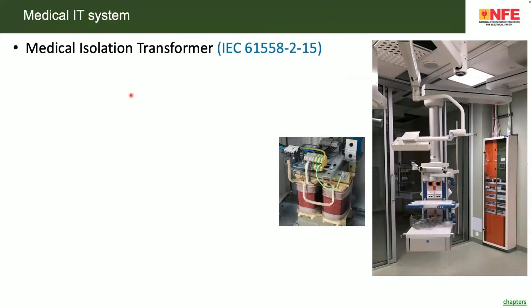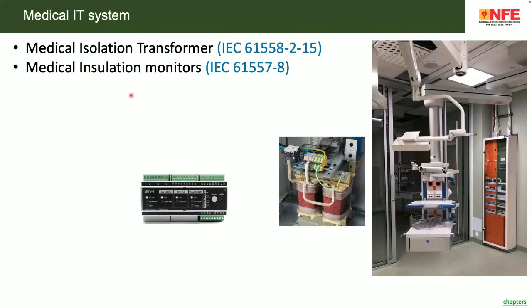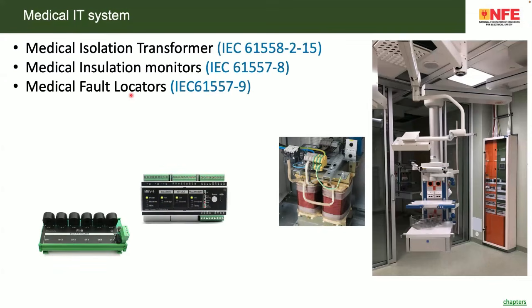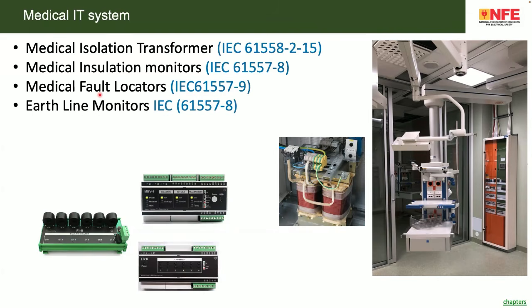It consists of a medical isolation transformer as per the standard, which is put on the bracket, a medical insulation monitoring device, and a medical fault locator. Please note that everywhere "medical" is added. An IT system is different from a medical IT system, or a medical IT system is different from a non-medical IT system. Medical isolation transformers are very special. It is not a normal isolation transformer. Medical insulation monitors are very special. It is not a normal insulation monitor. Medical fault locators are different from a normal fault locator.